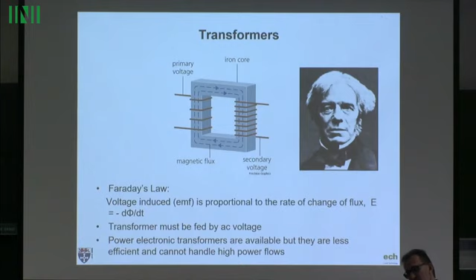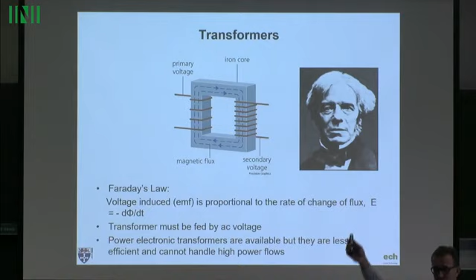There are power electronic transformers, but they are not as efficient, and they don't work at very high voltages. So in the house you may have a power electronic transformer, but you cannot imagine a power electronic transformer at the 400 kV level - it doesn't work.